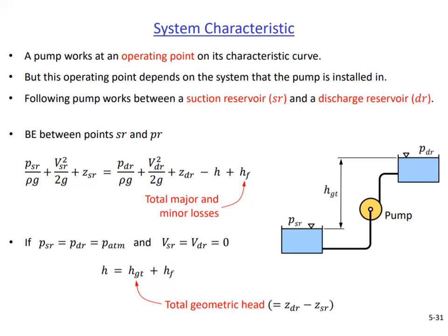This equation has both the pump head H and the head loss of the system HF. In the system shown in the slide, both reservoirs are open to the atmosphere. If also their free surfaces are large with negligible speed, the pump head can be related to the total geometric head and the head loss, as shown here. This is the system characteristic equation, but we need to write it as a function of the flow rate so that we can plot it together with the pump's HQ curve.